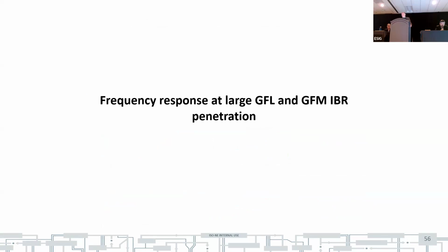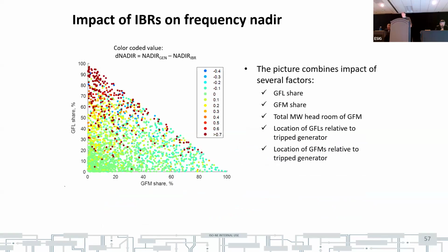Next set of results was related to if we combine grid following and grid forming inverter together in the system. And that is a picture where all results are shown in the same way. Each point is the result of one transient. So the axes are the percentage of grid following and grid forming IBR in the system. And the picture looks like a complete mess.